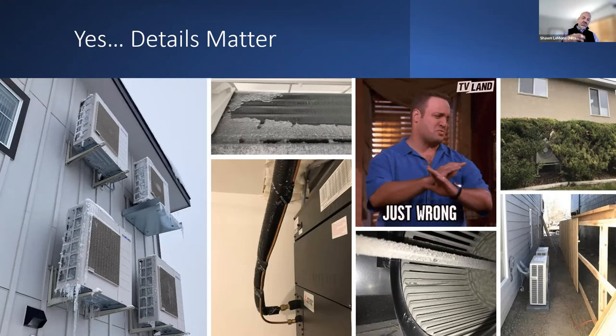Some other items in here. Looking at if you've got frost on the indoor coil, there's a good chance you're looking at a cross-wired system where the communication and the refrigerant flow are not aligned, they're not lined up in terms of, indoor system one is not necessarily receiving the right signal or the refrigerant at the same time. So indications of an issue. The line sets, both line sets need to be insulated. So on this image right there, that smaller line set is not insulated. That's the refrigerant piping that goes between the indoor and the outdoor.